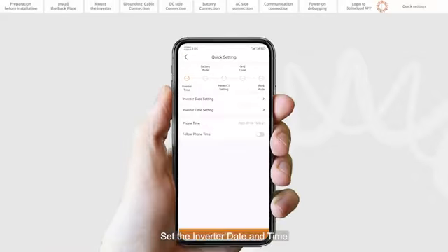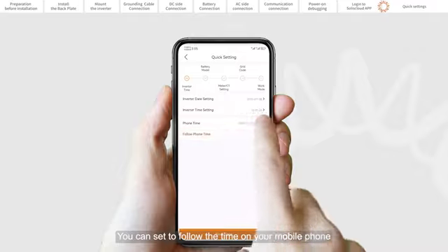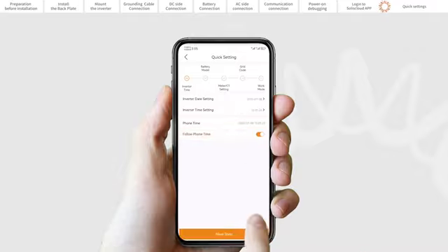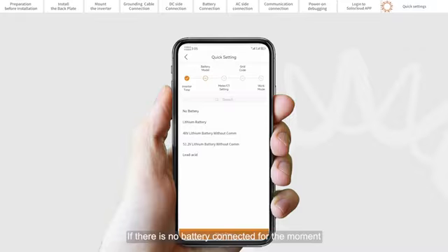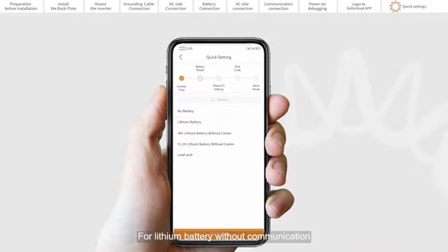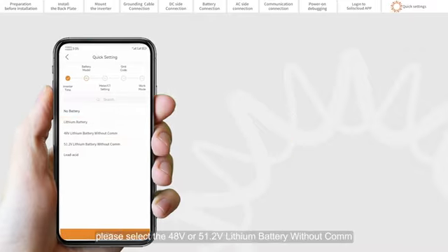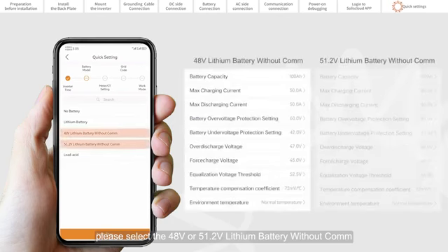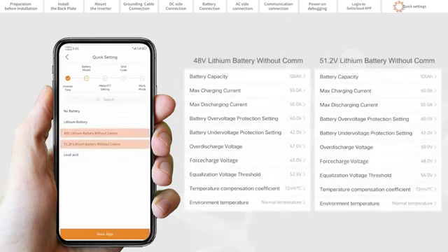Set the inverter date and time. You can set it to follow the time on your mobile phone. Set the battery model. If there is no battery connected for the moment, please select no battery to avoid alarms. It must be based on the battery model that is actually connected to the inverter. For a lithium battery with communication, please select Lithium LV. For a lithium battery without communication, please select the 48 volt or 51.2 lithium battery without COM.